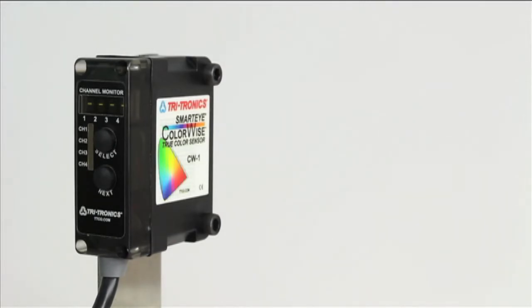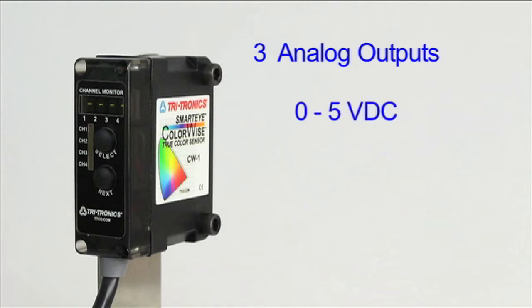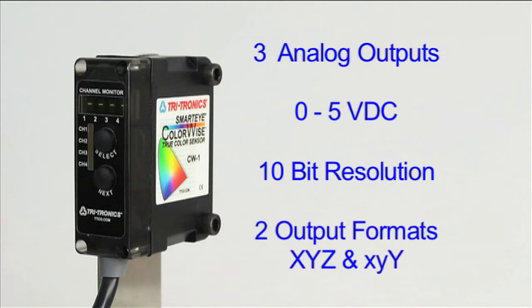The Tri-Tronics ColorWise sensor is unique in offering the user three analog outputs that expand its usefulness in solving applications. All three analog outputs are 0 to 5 volts DC and have 10-bit resolution. They can be used to output analog color information in one of two formats.